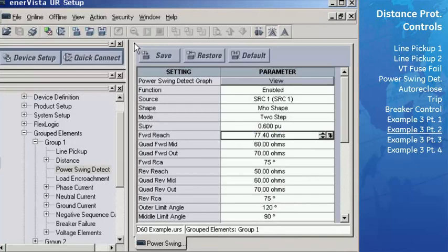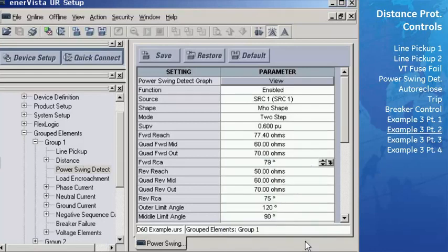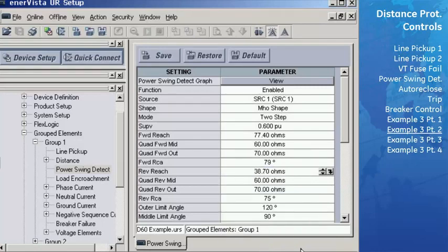The next 2 quad settings can be disregarded since we're using the Mho shape. Set the forward reach characteristic angle to 79 degrees. Set the reverse reach to the reverse source impedance, which is 38.7 ohms. Set the reverse reach characteristic angle also to 79 degrees.